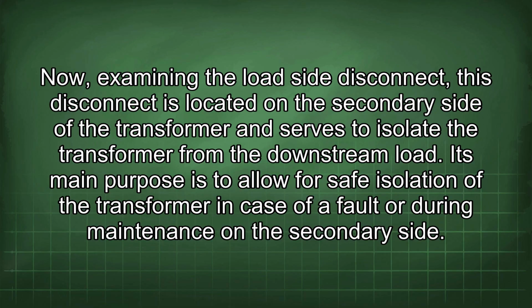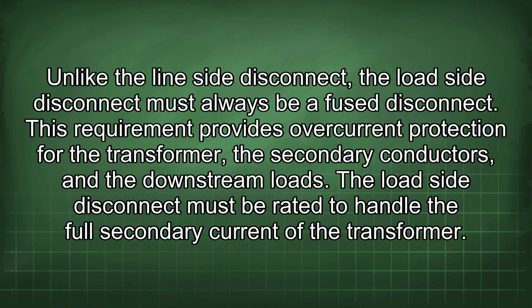This disconnect is located in the secondary side of the transformer and serves to isolate the transformer from the downstream load. Its main purpose is to allow for safe isolation of the transformer in case of a fault or during maintenance on the secondary side. Unlike the line side disconnect, the load side disconnect must always be a fused disconnect. This requirement provides overcurrent protection for the transformer, the secondary conductors, and the downstream loads.